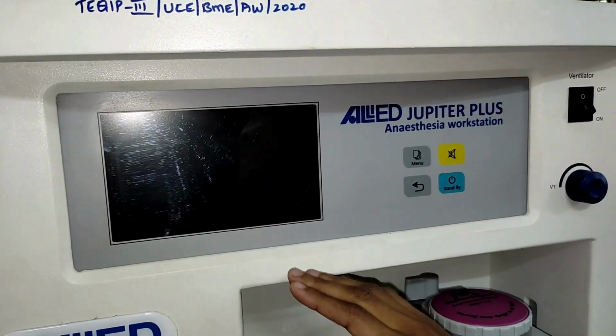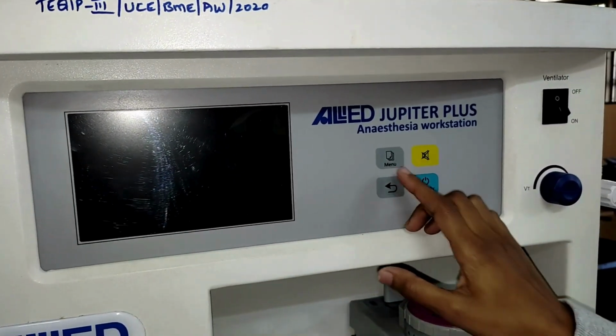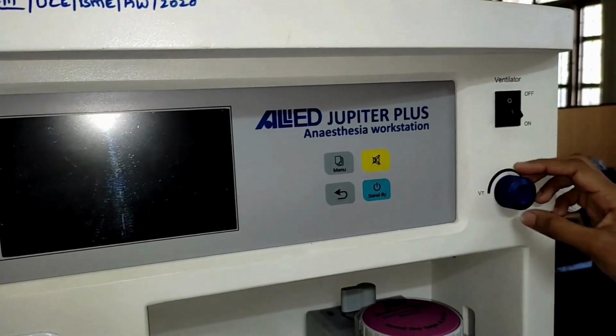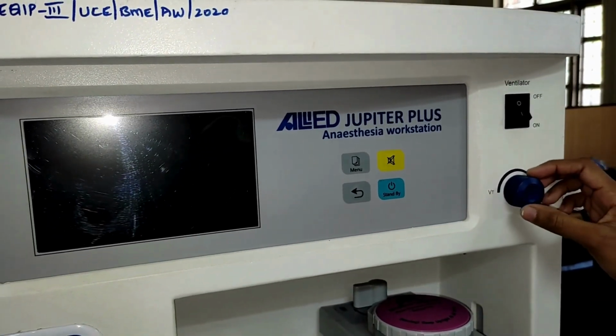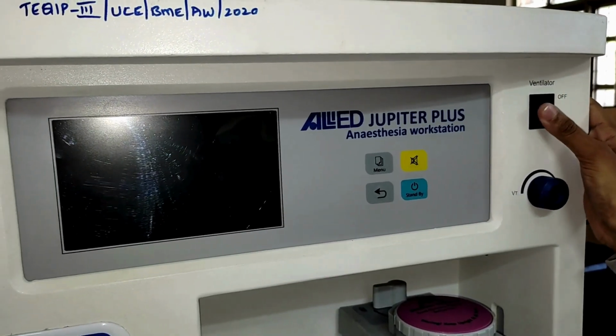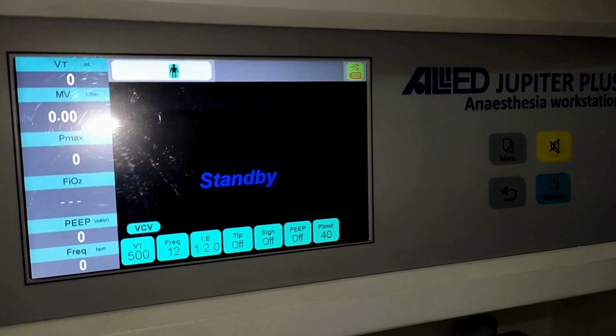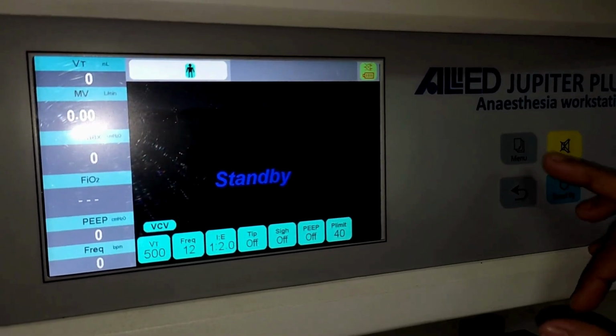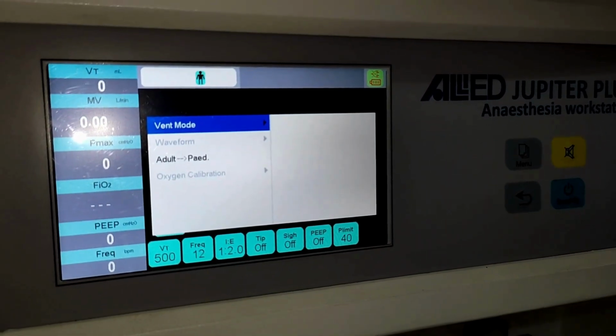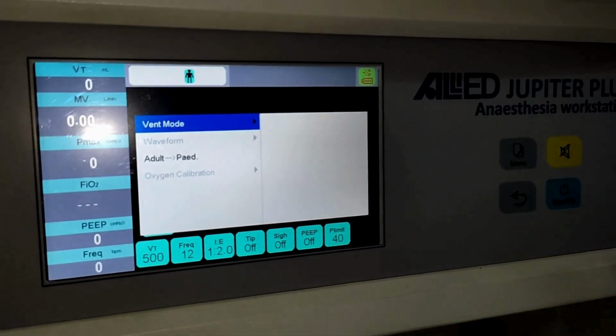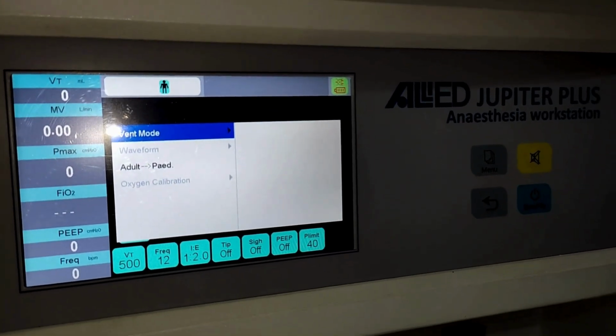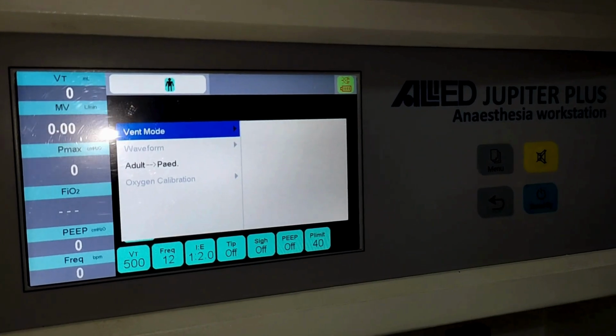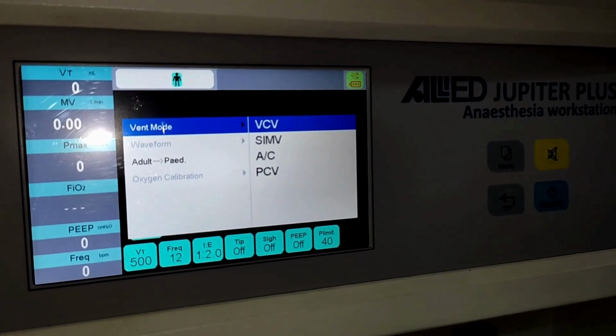In the ventilator section we have a 7-inch color TFT LCD display, 4 keys, those are menu, alarm silence key, back key and standby key. We have an encoder key which is used to navigate the menu. Here we have an on off switch to switch on the ventilator. At present the machine is on standby mode. To change the mode, we have to press the menu button, and here you can observe we have ventilation mode. By clicking on that we can change the ventilation mode.